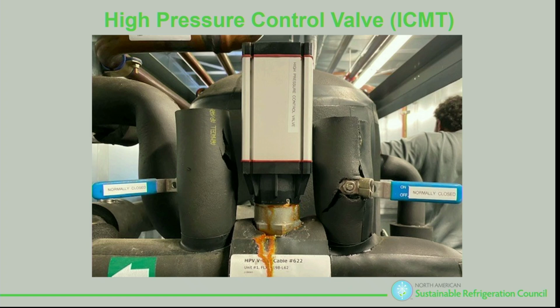That's an easy valve. If it fails me, so let's say I'm running a high head for no reason, or maybe that valve is stuck closed, and I'm getting high head because it's shut. Maybe it's too far open, it's adding too much pressure in my receiver flash tank, and I have some of that going on, right? And so now I have a couple of things I can try. I can take it to manual. We had a valve fail here in California. It burned up, we couldn't get one, supply issues, so we ran it for 3 months in manual.